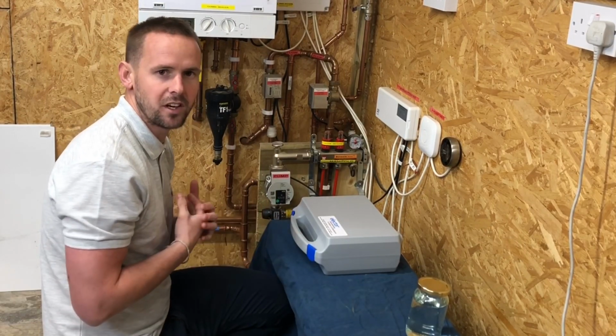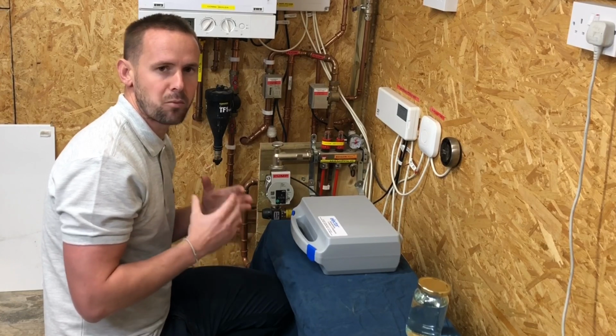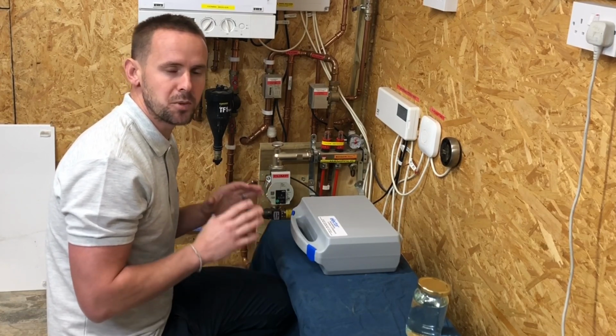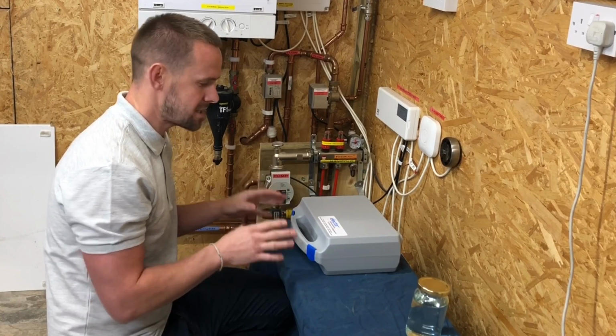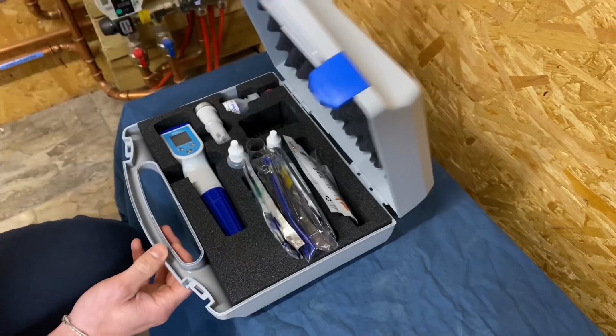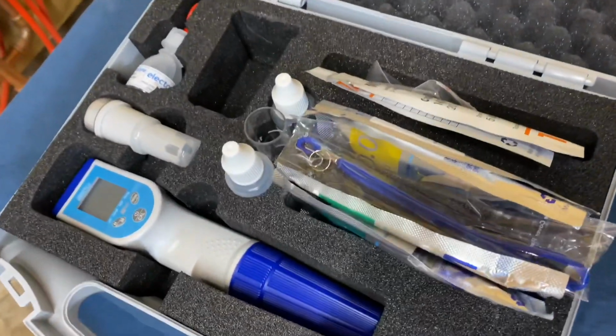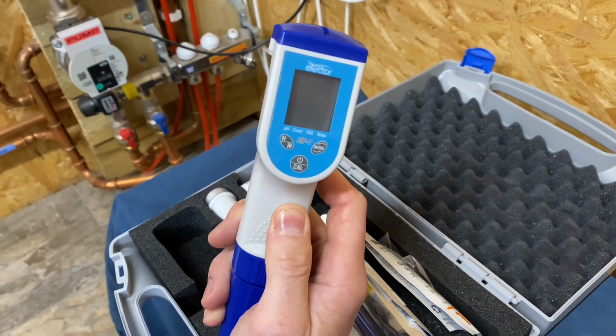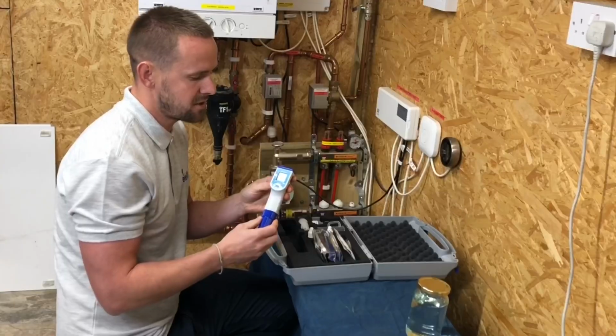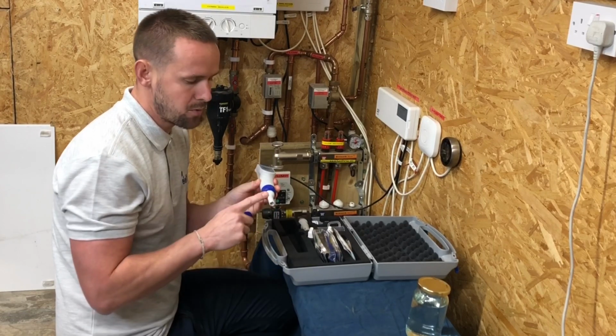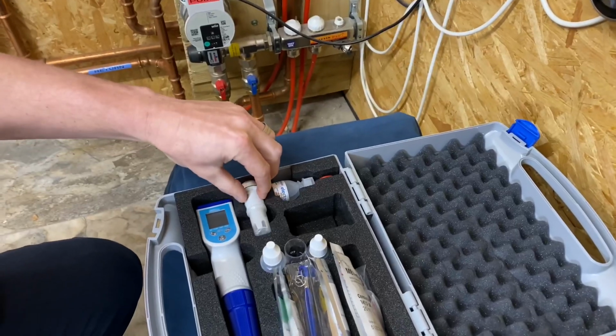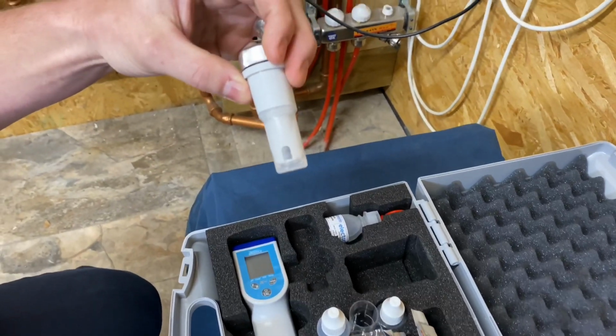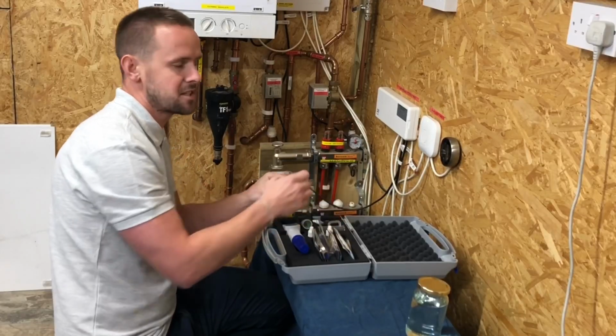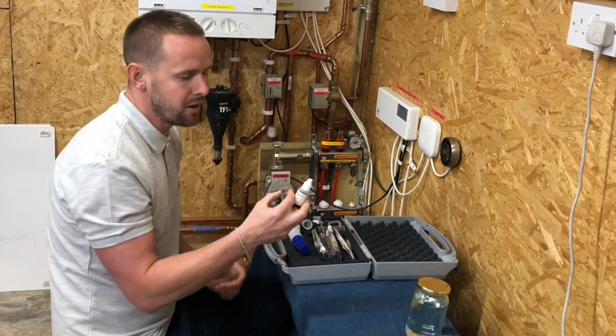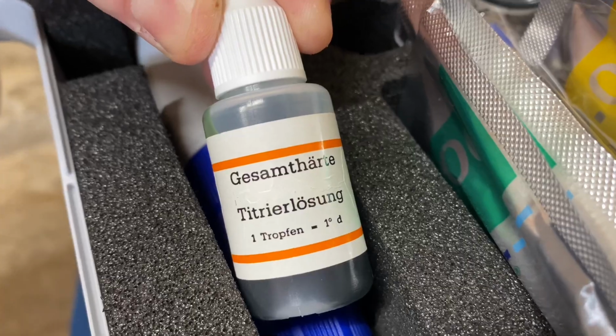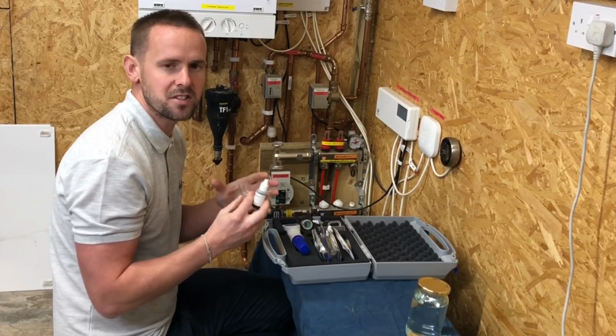The reason I personally like VDI 2035 is because we're working with specific parameters, and they're parameters that we can check on site, so we don't need to send off for any water samples. The test kit itself, the MP7, is very easy to use. So the test kit comes with the MP7 meter. So this will do the TDS, the conductivity, and the salts from the same probe. We can change the probes out and also check our pH. And then we've also got a simple drop test to test the total hardness. So if we get these parameters correct, we basically won't have any corrosion within our system. So it's very, very simple to monitor.